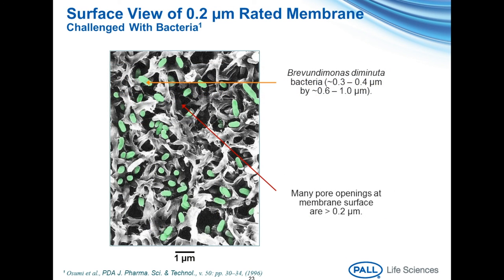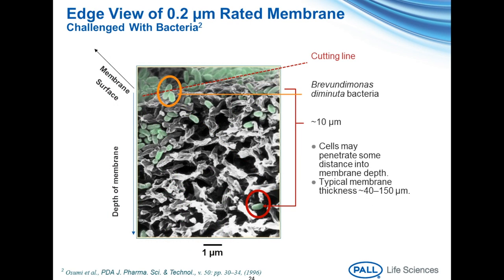Here we have a surface view of a filter matrix. Many of the pore sizes at the surface of the membrane are greater than 0.2 micron, yet this membrane carries a 0.2 micron rating and has retained the challenge organism Brevundimonas diminuta. Brevundimonas diminuta is used as a standard challenge organism by Pall Corporation to demonstrate bacterial retention. This picture is of a membrane cutaway under bacterial challenge, showing B. diminuta retained both on the membrane surface and within the matrix, having penetrated to a depth of 10 micron.